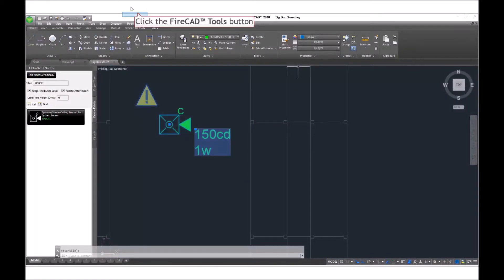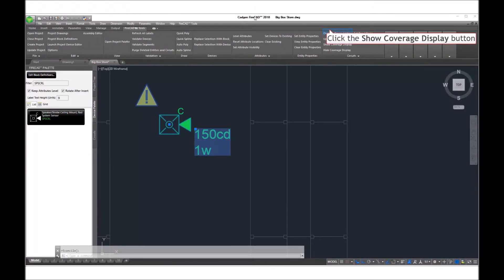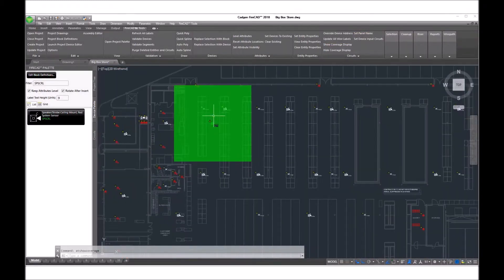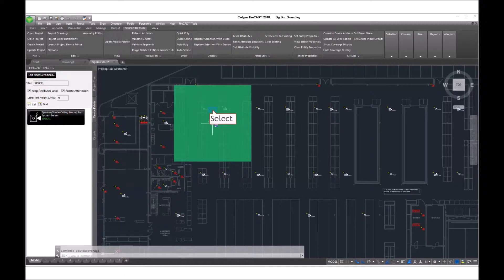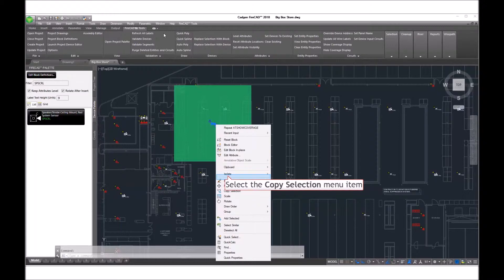First, we select the device and then from the FireCAD ribbon, we choose to show coverage. This shows us the coverage of the strobe at the specified candela rating.